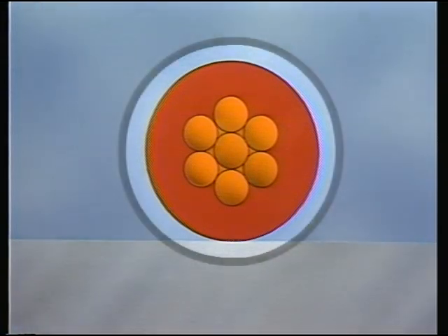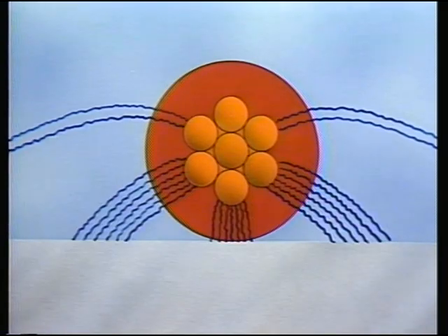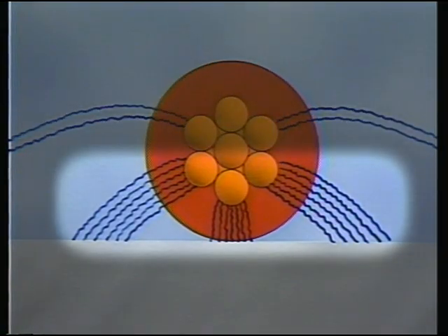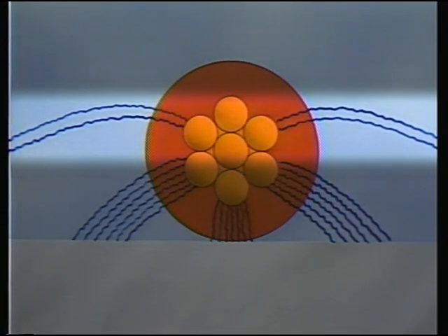Here we have a single-stranded conductor. The cable is shown near ground potential. When voltage is applied, the cable insulation becomes stressed. The radiating lines are lines of stress pushing outward from the conductor to the cable's insulation. Now, as you can see, the stress lines are going almost straight down at the bottom of the cable and are bending towards ground near the top of the cable.